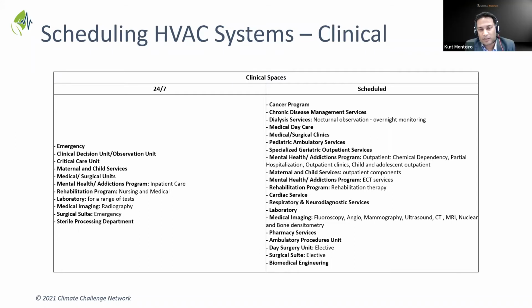One of the things I'd say is that when designing the air handling systems, we made sure we had air handling systems that weren't serving 24/7 areas mixed with areas and programs that could be shut down. The project-specific output spec listed when departments would be running and what the expectations were. It didn't say the exact start and end time, but gave us a range of operating hours and whether it would operate on weekends. So when grouping spaces together to serve off the same air handler, we made sure we weren't mixing those types of spaces up.